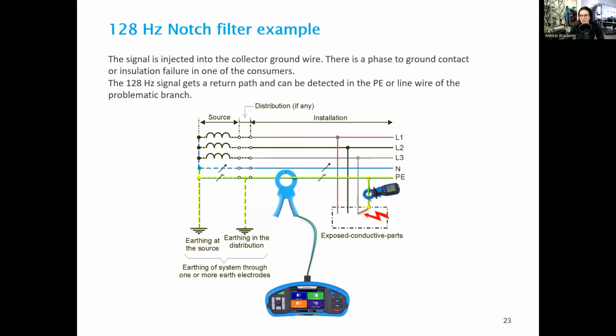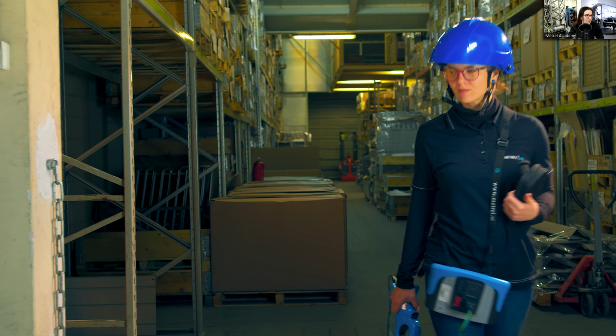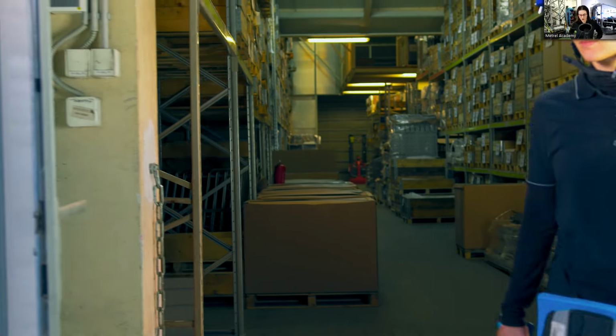Now, to look at the diagram of the problem that I described earlier. We are generating the signal into the common protective earth wire, and here in the drawing there is only one consumer, but there can be multiple in the system. Only where there is an installation problem is the signal going to have a return path, so that when we clamp the PE wire we find that the signal is flowing into this consumer, and we know that we have found our installation fault. So here is the video of how this is done.